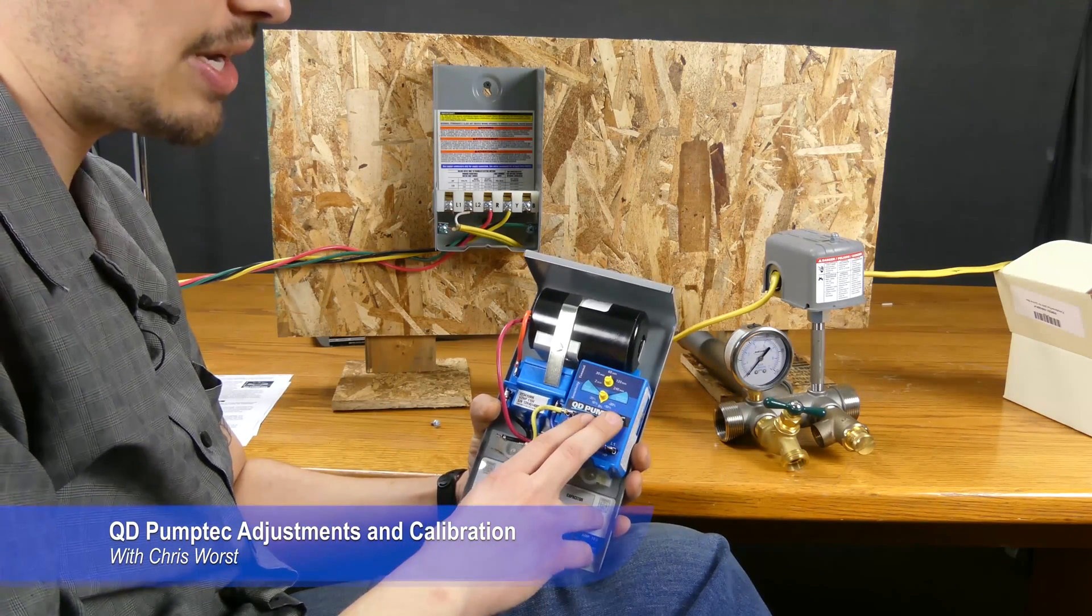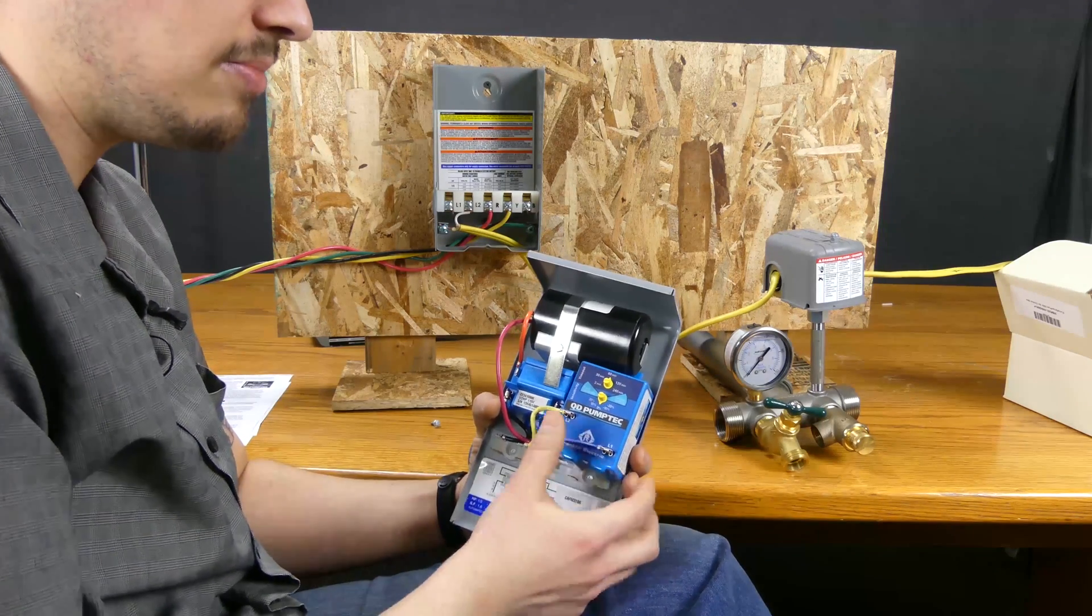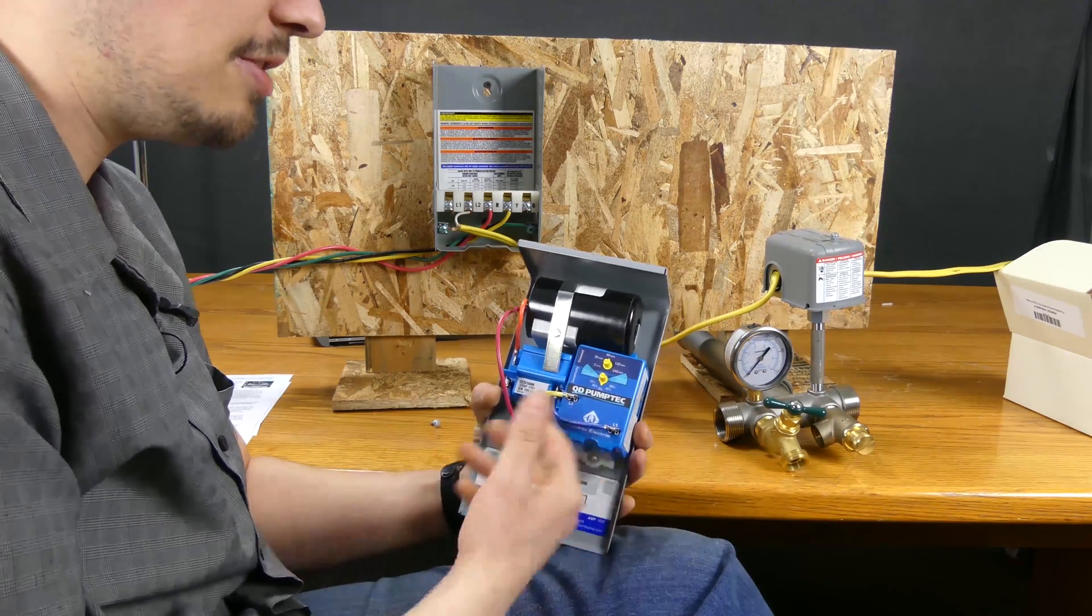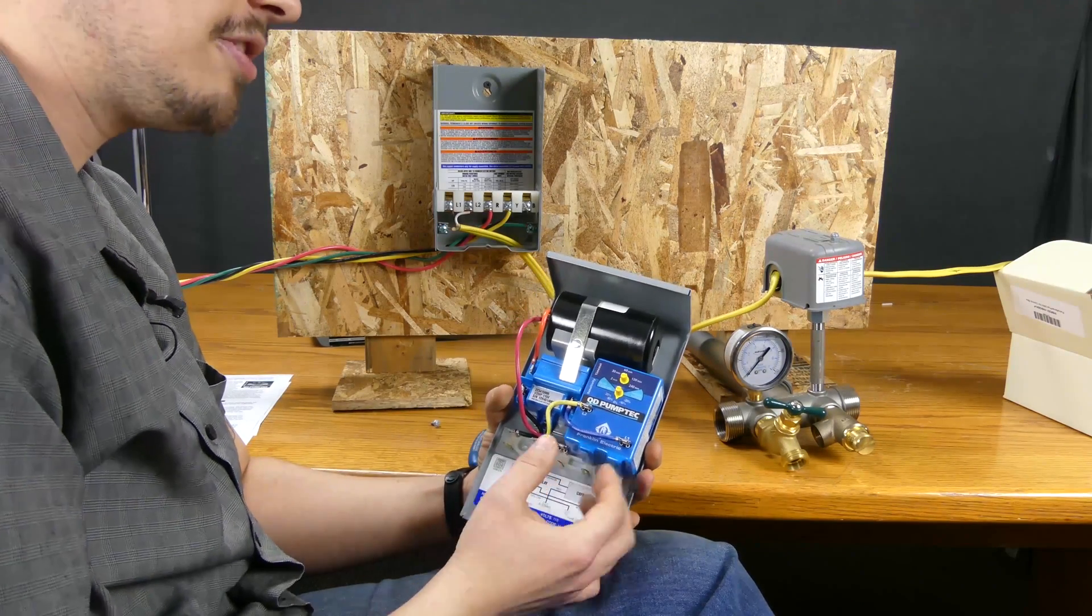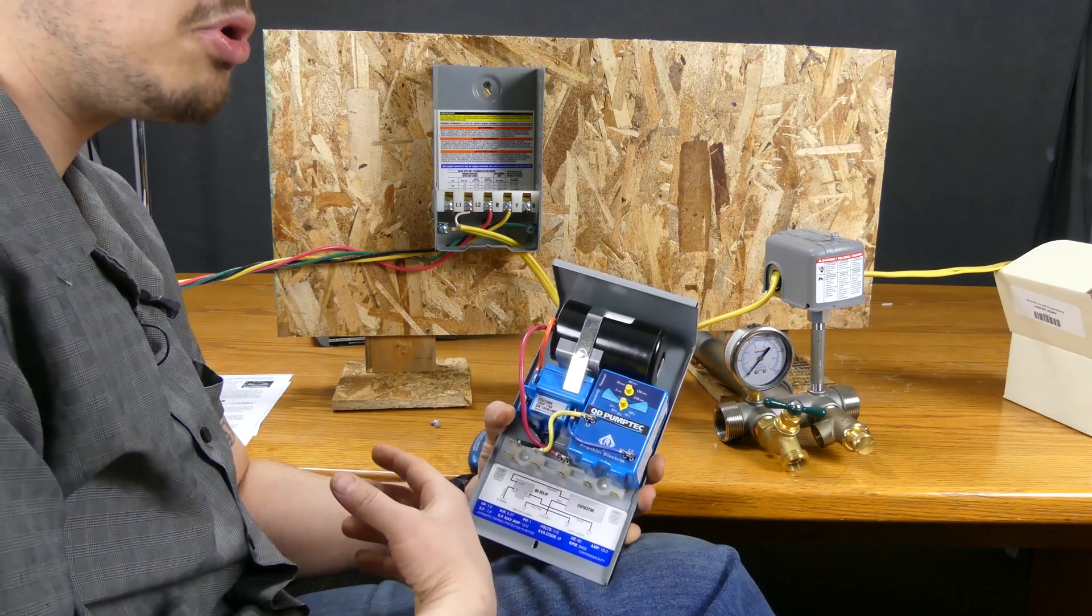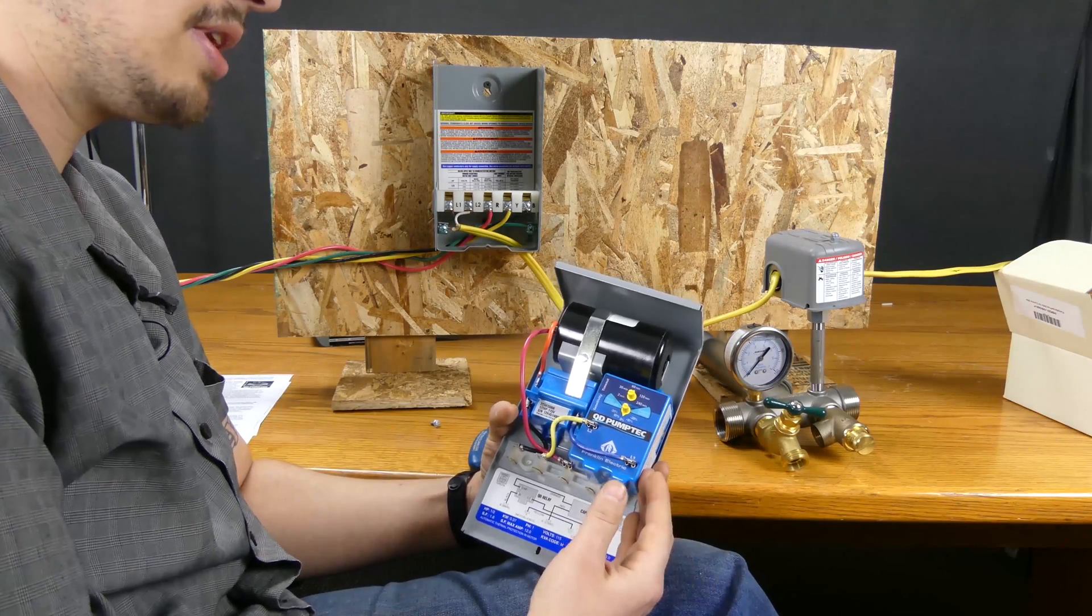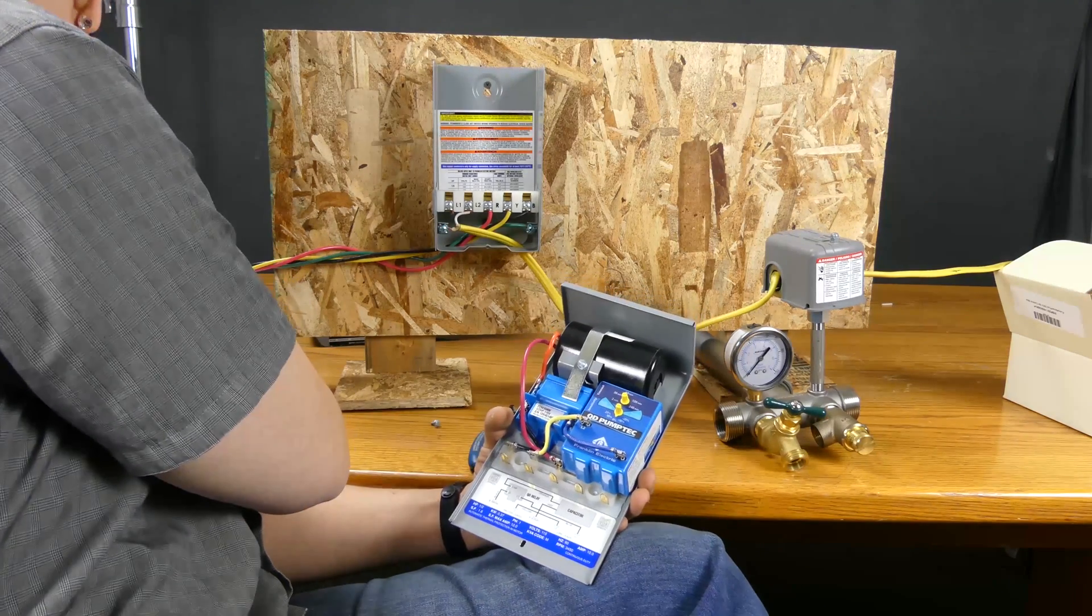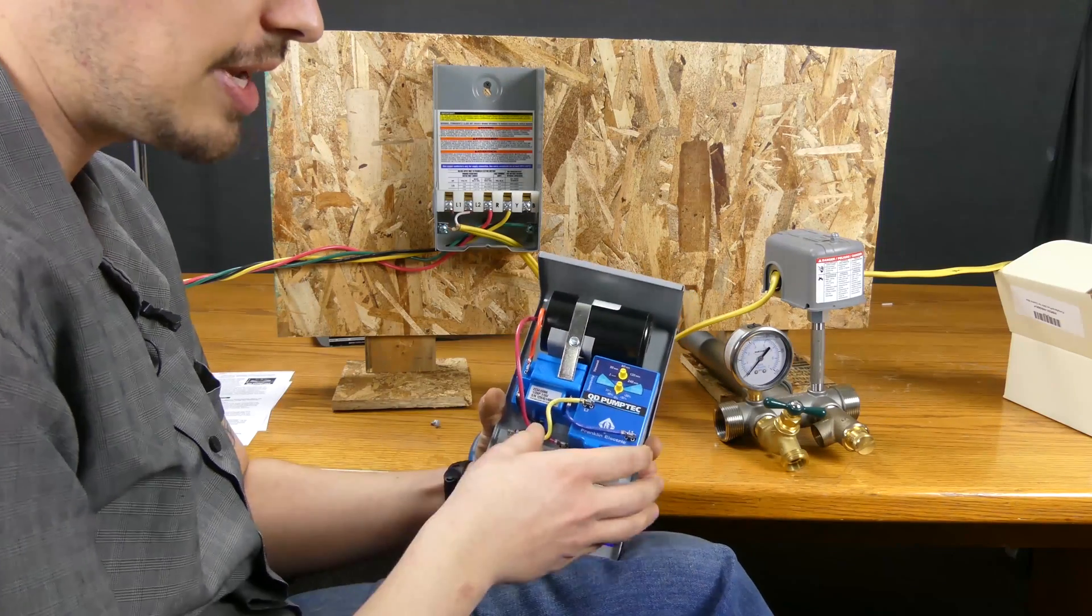Now the first thing I want to preface this with is when it comes to these QD Pumptecs, generally probably 70 to 80 percent of the time the factory settings are going to be fine and there's going to be no adjustment needed. But if you find that you need to adjust yours you certainly can, and you're going to find most commonly you're going to need to adjust these if you're using it with a motor that's not a Franklin electric motor. But basically if it's a Franklin electric motor one-third through one horsepower, I believe through one and a half horsepower, this should be set up and shouldn't take any adjustment.